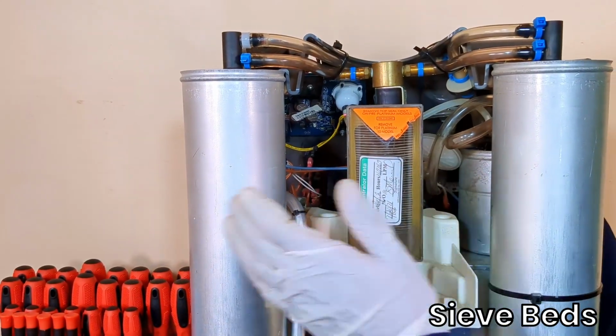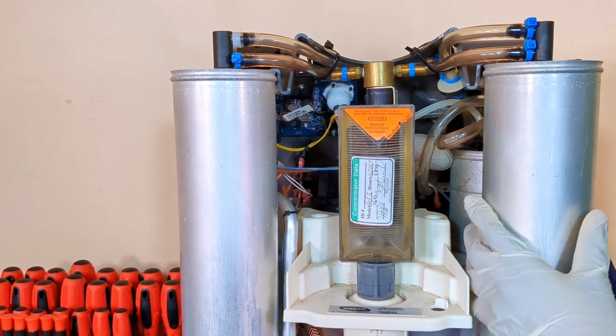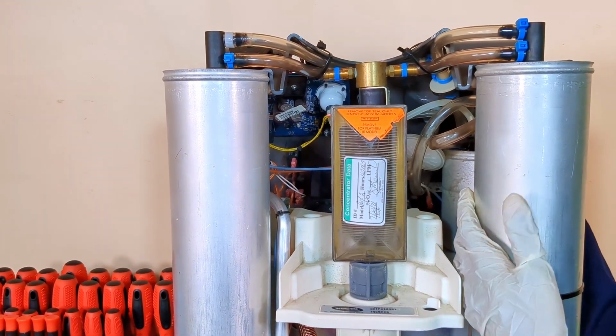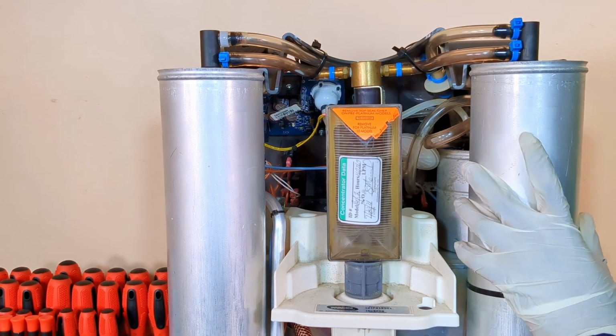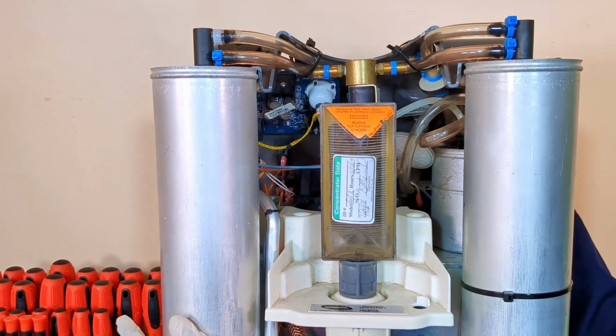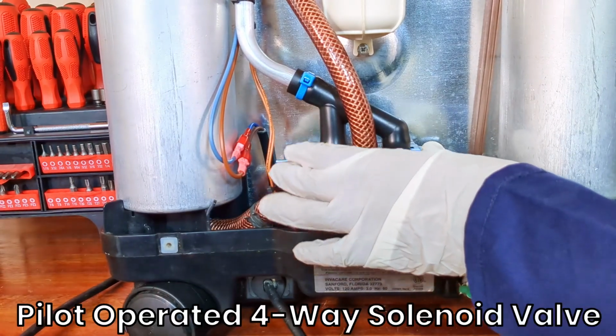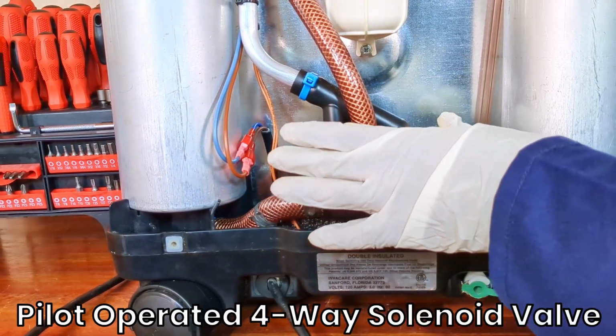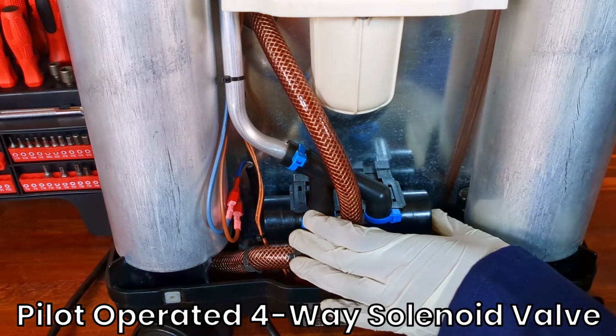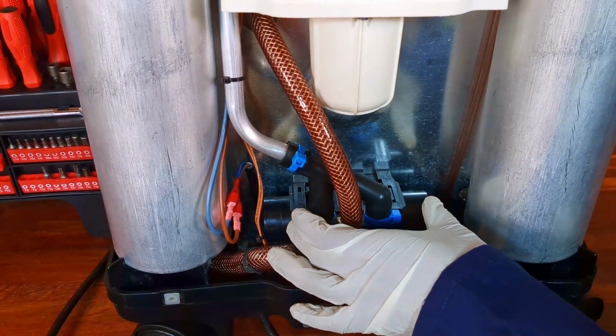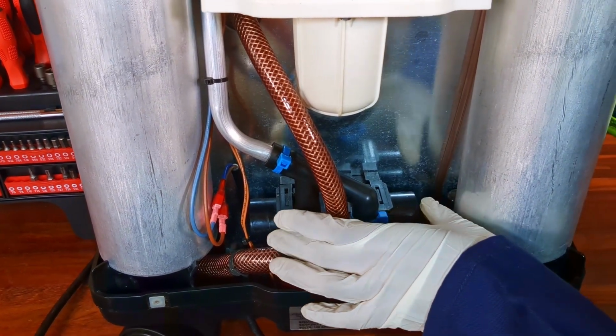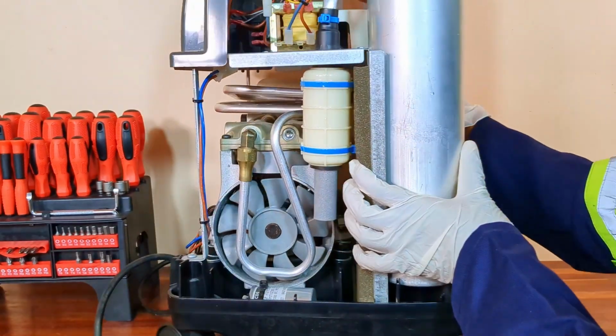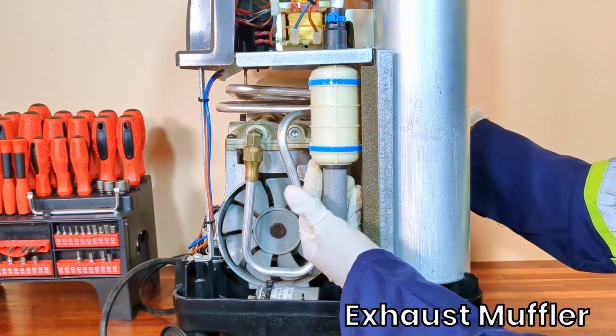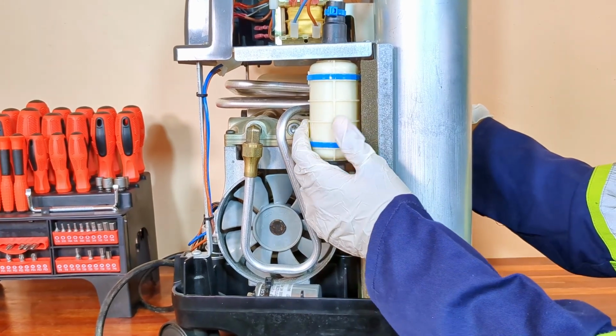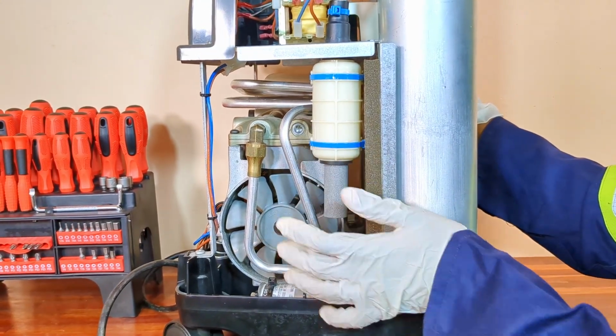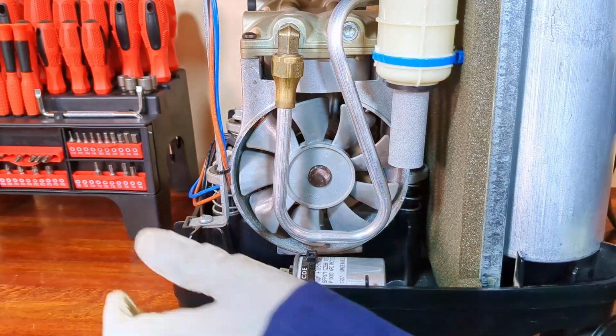These are the 2 sieve beds. These sieve beds contain a material known as zeolite, which absorbs nitrogen as air passes through them, thereby concentrating the oxygen. This is the pilot operated 4-way solenoid valve. This valve is responsible for the switching of airflow between the compressor, the sieve beds, as well as the exhaust. Connected to the solenoid valve is the exhaust muffler. This muffler is used to reduce the sound that is produced during the nitrogen purging.